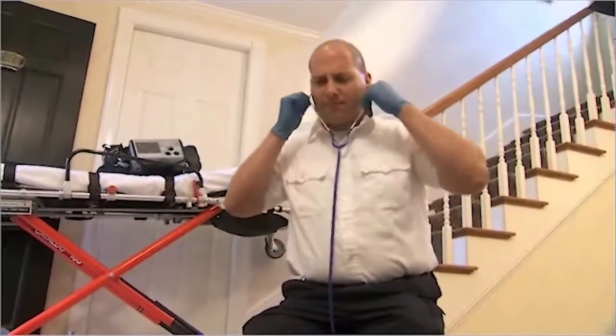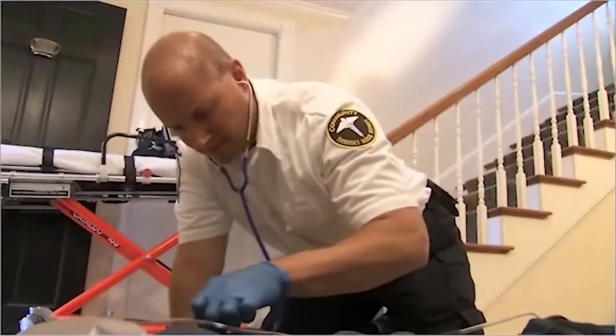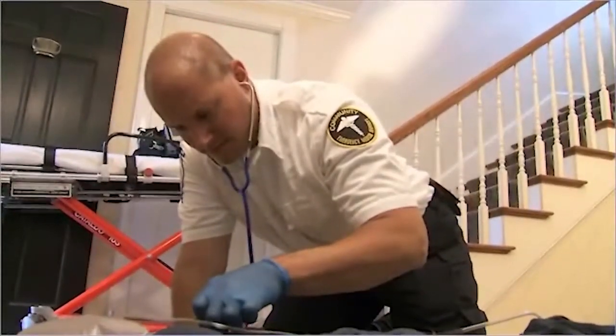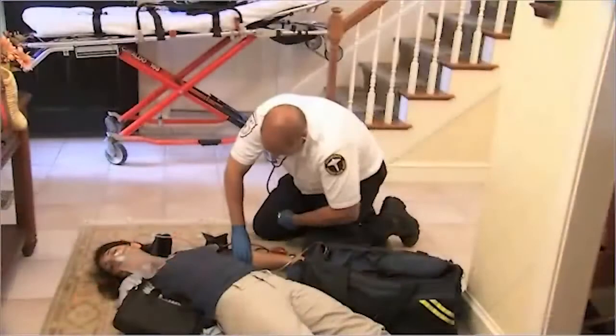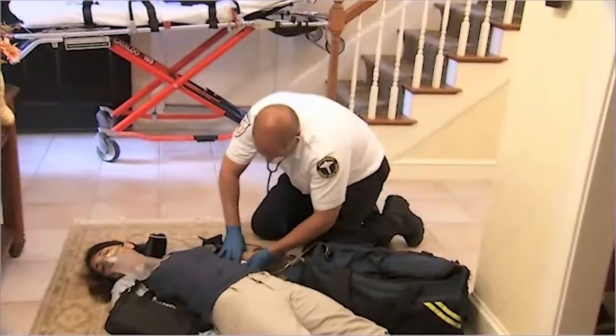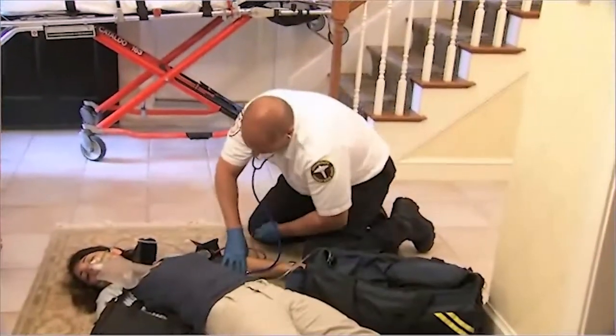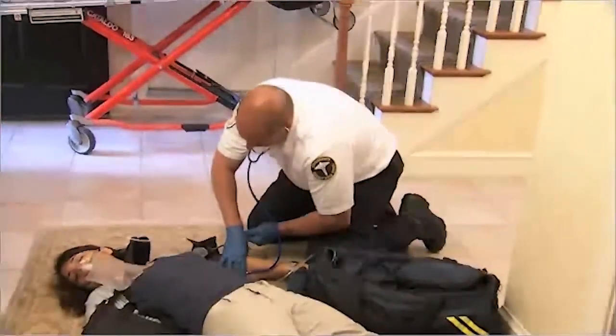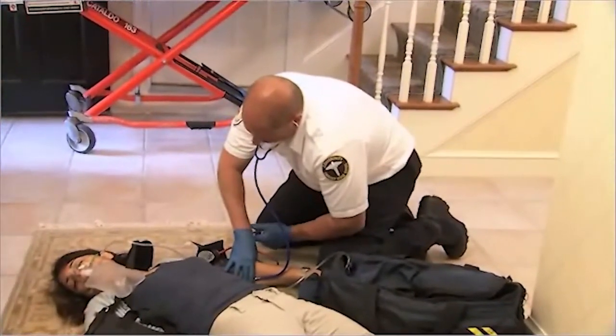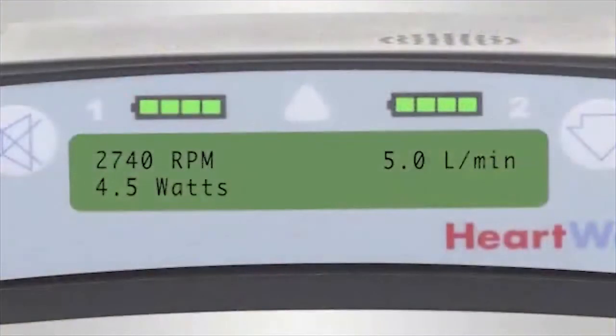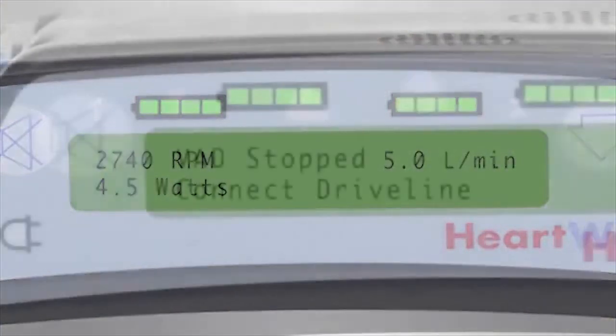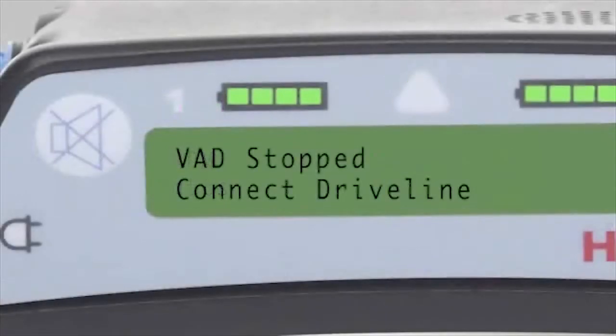Chest compressions may pose a risk due to pump location and position of the outflow graft on the aorta, so use clinical judgment when deciding if CPR should be performed. If the patient requires CPR, confirmation of device function should be performed at the hospital. The HVAD pump, if working properly, should be able to circulate blood. If, however, there are alarms or indication from the controller that there is no or little flow through the VAD, a couple of steps should be taken.